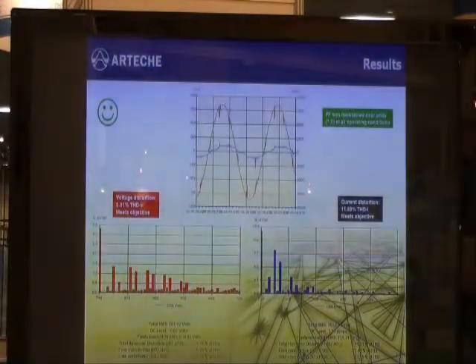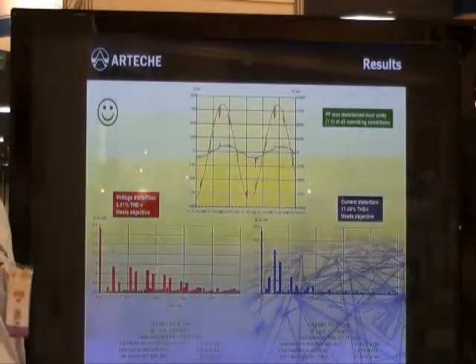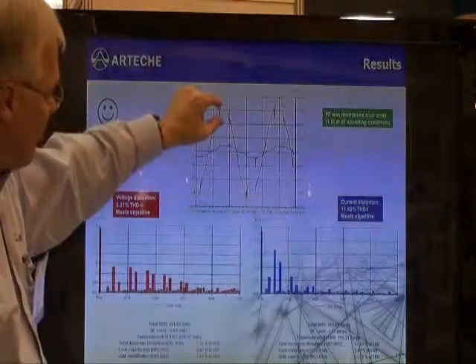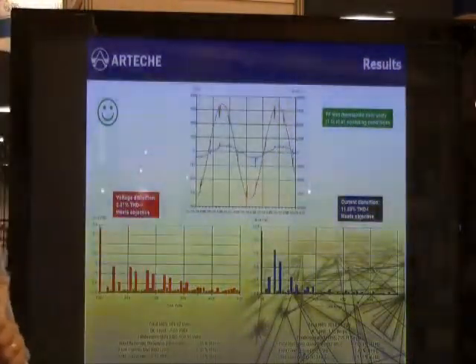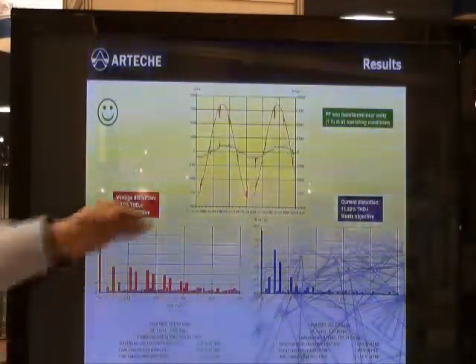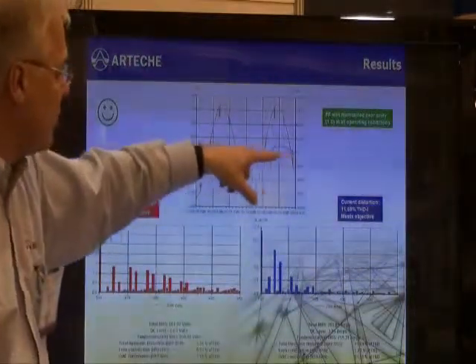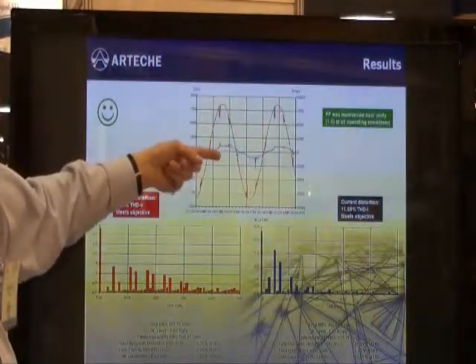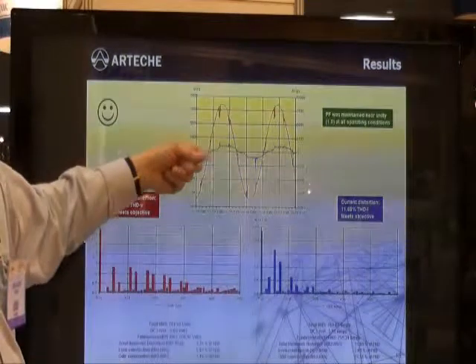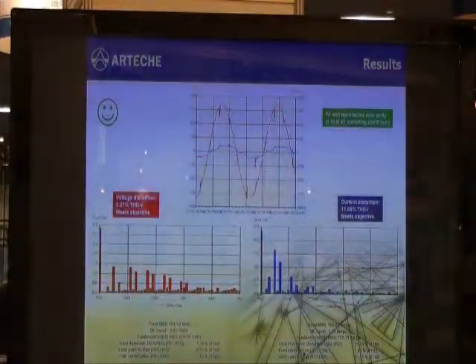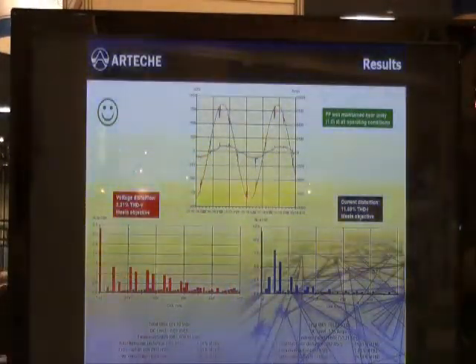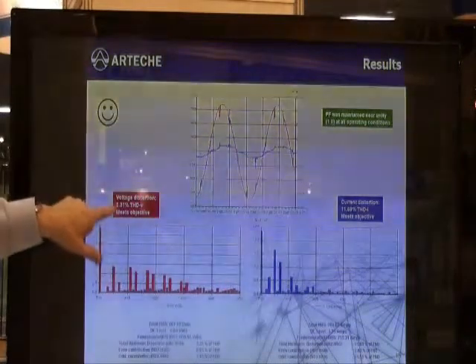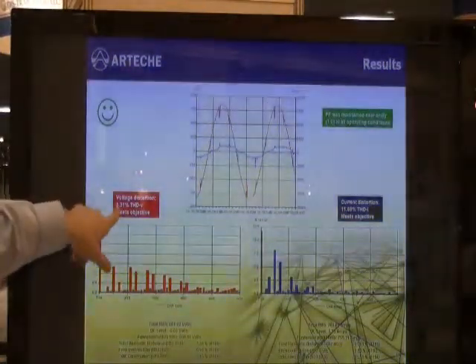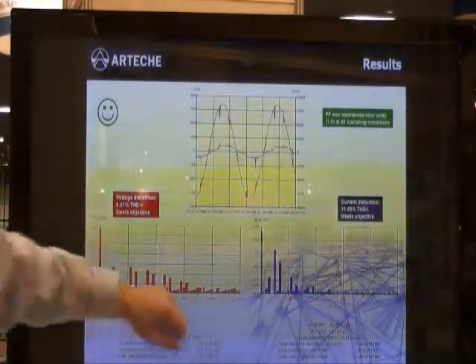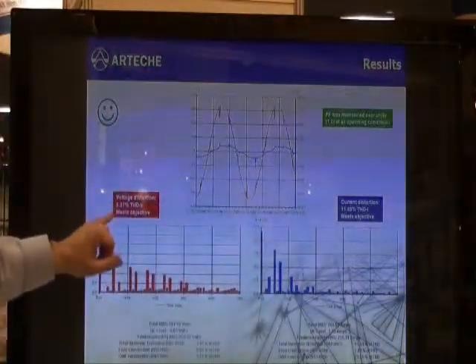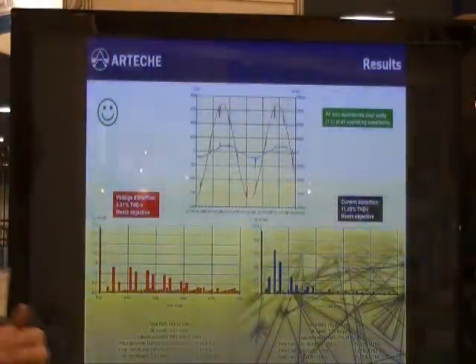So now the results after we applied the SmARTvar system are that the voltage notches are reduced to very low levels so that they are far away from the zero axis. So they no longer provide any danger of switching or providing a false signal to other equipment. And the harmonic spectrum is such that now the voltage distortion is only 3.3%. The objective was 5, so the objective was obtained here.